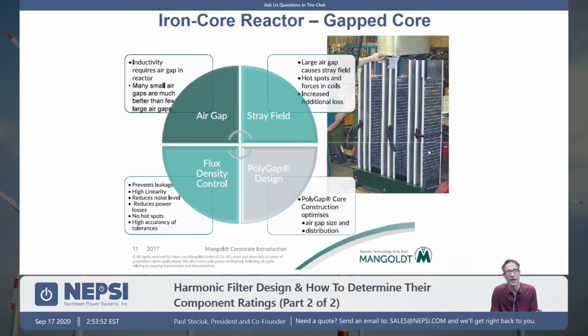There can be a desire to reduce the number of gaps. That in itself reduces the cost. Okay, reduce the number of gaps, reduce the cost. But the quality of the reactor is not as good. If you have a larger gap, you have more stray flux. More stray flux means more heat.